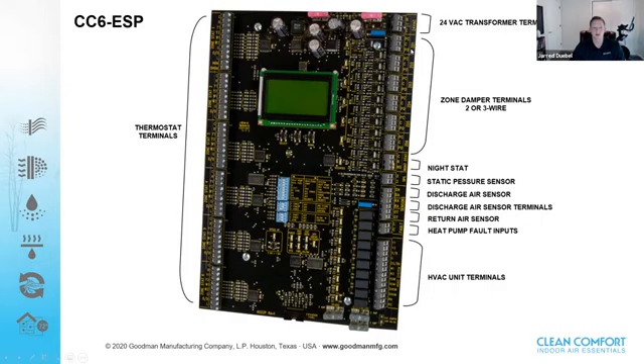So what that means is if, let's say zone 1 and 2 are calling, those are going to be illuminated green, solid green. I know those zones are calling when I see those LEDs illuminated. Let's say zone dampers 3 through 6 are blinking green. Well, then I know those zone dampers are modulating open to relieve static pressure. This is where the night stat's going to install.